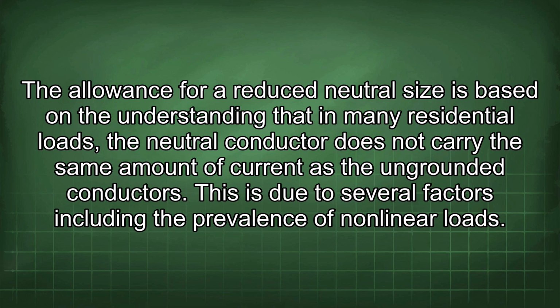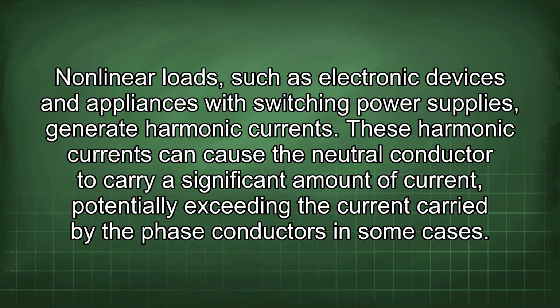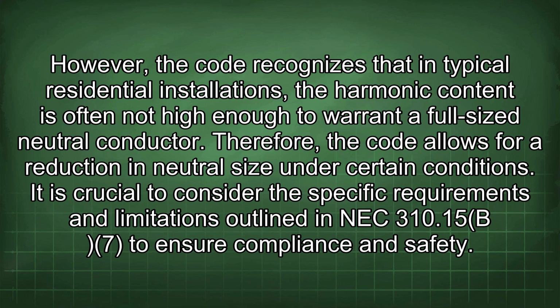This is due to several factors, including the prevalence of nonlinear loads. Nonlinear loads, such as electronic devices and appliances with switching power supplies, generate harmonic currents. These harmonic currents can cause the neutral conductor to carry a significant amount of current, potentially exceeding the current carried by the phase conductors in some cases. However, the code recognizes that in typical residential installations, the harmonic content is often not high enough to warrant a full-size neutral conductor. Therefore, the code allows for a reduction in neutral size under certain conditions.